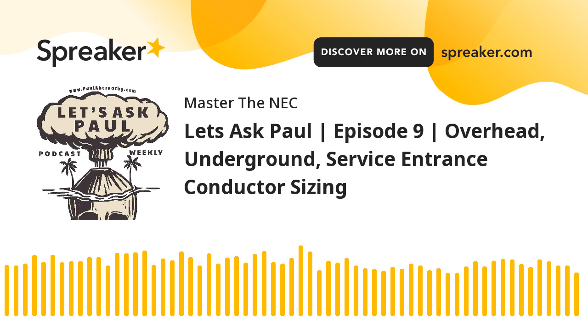So we've got some exceptions to this rule, and the ones we're going to deal with are exception number 5 first. Now, this is an exception that's saying, you might have an overcurrent device providing the overload protection for these service conductors, but it's possibly larger than the rating of the service conductors. And we know there's an allowance in the code under 310.12 if you're dealing with a service or feeder that is 100 to 400 amperes, not over 400 amperes, that supplies 100% of the load on that service or feeder, supplying equipment like a panel that handles 100% of the load. Then I'm able to use what's called the 83% rule, or the reduced conductor size, and it's still considered protected. Well, if you didn't have exceptions here, then we could not use that allowance, because that rule is saying my conductors can be smaller than what the overload protection would be. And this rule here says you can't do that.